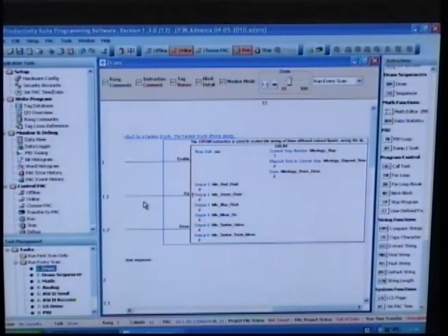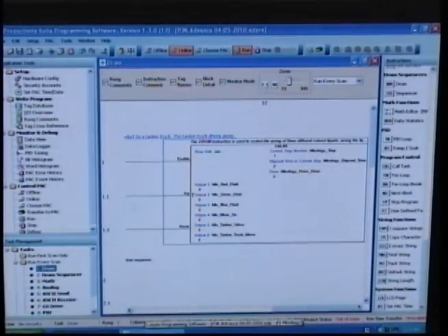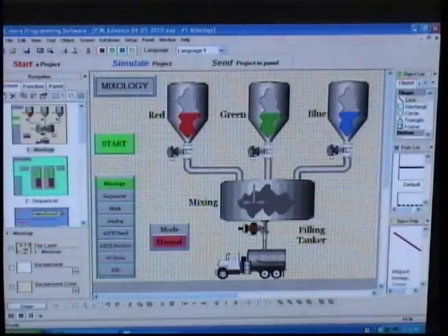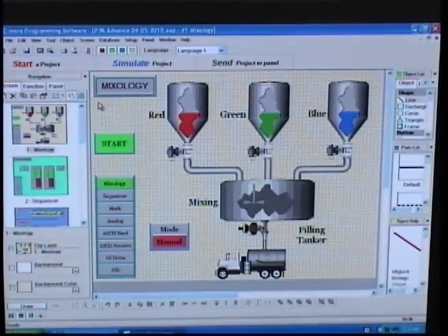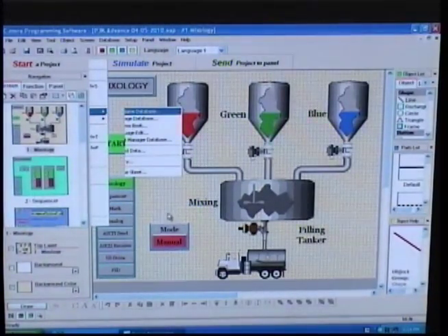And also with those tag databases, if you go to the next slide for our reference, we can also export. So once I've set up my programming, I can sit here and do an export tags, and I'm not going to go through the whole thing, but I can create a CSV file with all the tag names. Make sure, because I always forget, if you want to include your IOs, check the little check box to include the IOs here, and create a file name and a folder location, and that's kind of how you do that. And then real quick, once I've created those tags, if I'm going to use them in C-More, here's part of my C-More screen development, I can actually come in here and import that tag name database.